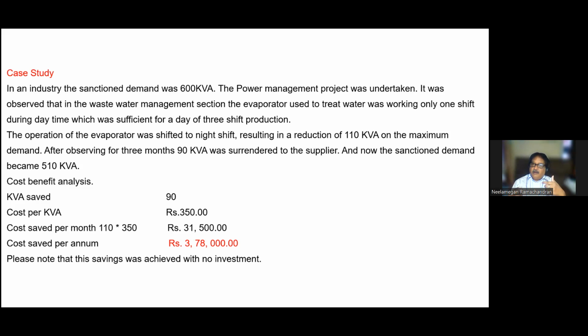So that one shift operation was shifted to the night shift, and the evaporator runs in the night shift. That 90 kVA, we were able to save 110 kVA. We did this regularly for 2 to 2.5 months and saw a reduction of 110 kVA in maximum demand. So, to be on the safer side, we kept 20 kVA and surrendered 90 kVA to EB. By running the evaporator in the night shift instead of the general shift, we were able to achieve this much saving. So this can be thought of.